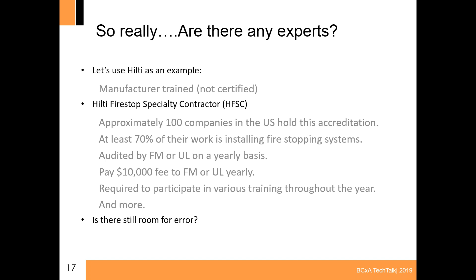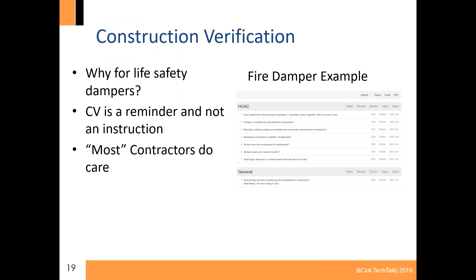So how do we help from a commissioning standpoint? Probably using a couple of big tools we all have in our tool belt. One is actually participating in or leading pre-installation meetings pertaining to fire stopping, and even fire smoke damper installation. Another is utilizing construction verification forms as little reminders to the contractor, have I done this, have I done that? And should there be a CV form specifically for fire stopping, and if so, what would we want to put on it?